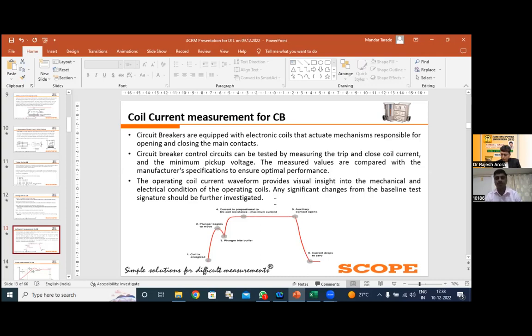That is the basic purpose of the coil. If my screen is visible, here I have highlighted 6 points. The first point is the energization of the coil. The second point is the plunger begins to move. The third point is the decrease in the current of the coil, where the plunger hits the buffer. Next, the coil reaches the maximum current value, or saturation, and after that, the auxiliary switch immediately changes over. Okay, and the coil current reaches 0.